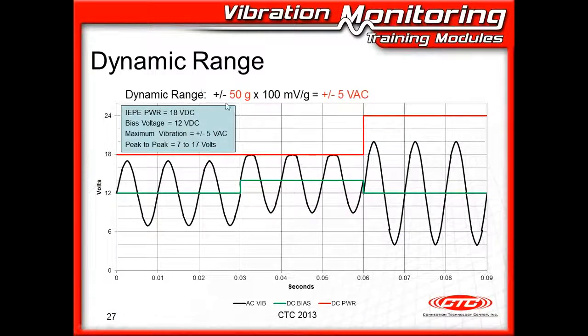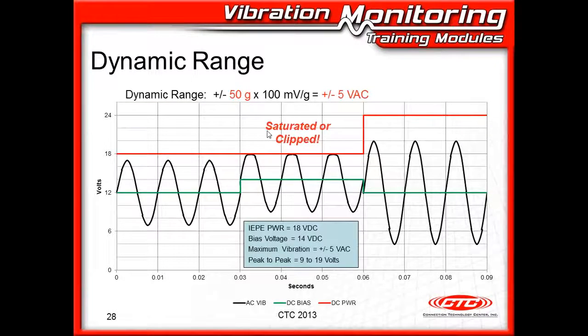This dynamic range can trip you up a little bit. And you know, we looked at some sensors here that have 50 Gs of dynamic range, which means at 100 millivolts per G they'd have a plus or minus 5 volt AC output. And that sounds nice, but it's also dependent on your power supply. So here I have a power supply that only puts out 18 volts, and that's represented by this red line. And my bias voltage is right in the center. It's at 12 volts DC, so my bias voltage is centered right where it should be. And my AC signal, plus or minus 5 volts AC, nicely rides around my bias voltage, and it doesn't exceed my power supply voltage, nor does it exceed 0 volts. So this is a very happy sensor here. Even at its maximum vibration, everything's working well.